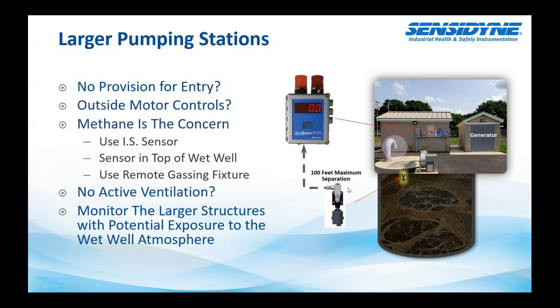In a Div 2 area, you can, again, I'm not your classification expert. These are things that you want to consult with engineers on to make sure you're doing the right things. But we do offer this remote mounting kit as a Class 1 Div 1 area with poured connections. The sensor itself is IS, so in a Div 2 area, you shouldn't need all that extra, but we do offer it if it was of a concern. It's not that much more money than the regular remote mount kit, so it's probably just a good practice if there even is a chance of that being an issue.